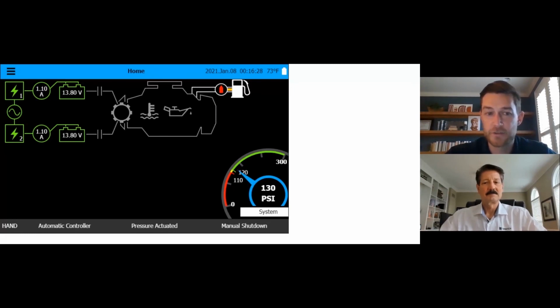Next to that, it shows either the automatic or non-automatic. Automatic is the majority of the panels that we're using. Pressure actuated, meaning it's going to start on a pressure drop. And then the manual shutdown, meaning you have to come in there and manually stop the pump. It's going to run indefinitely until somebody hits the stop button, which can also be done as an automatic shutdown. And then we have the same date, time, and temperature settings up there on the top right.